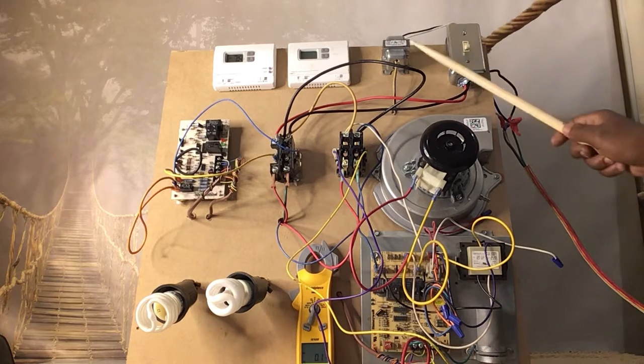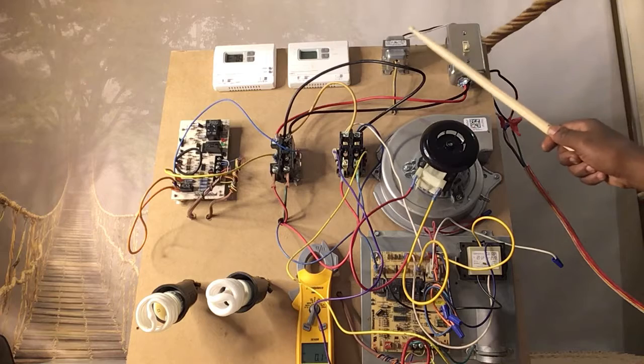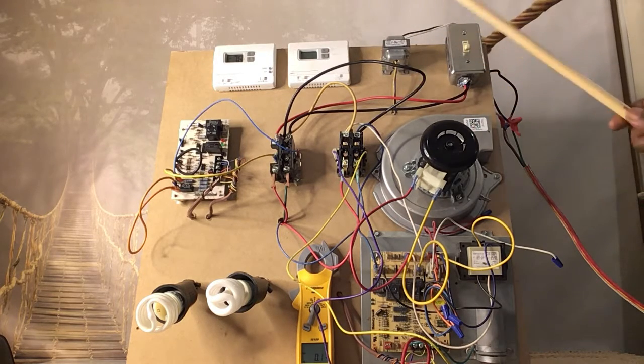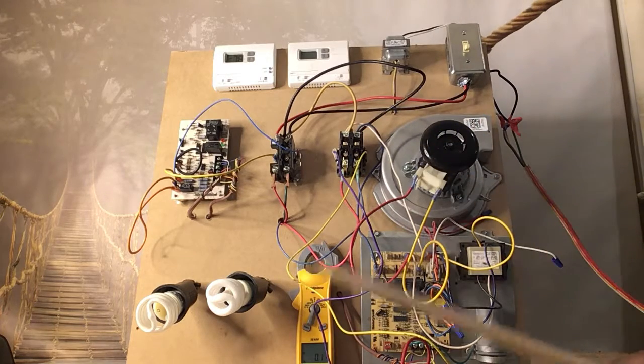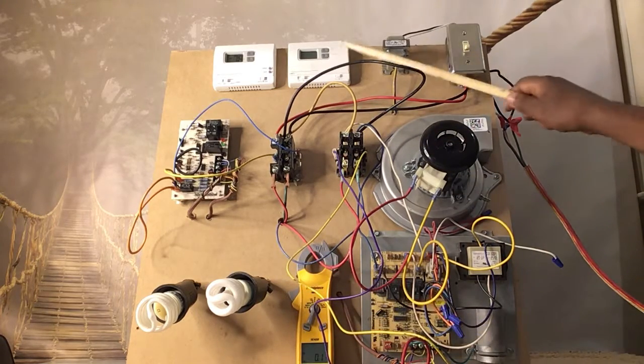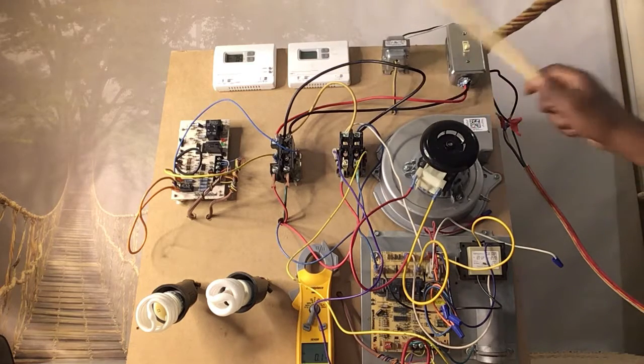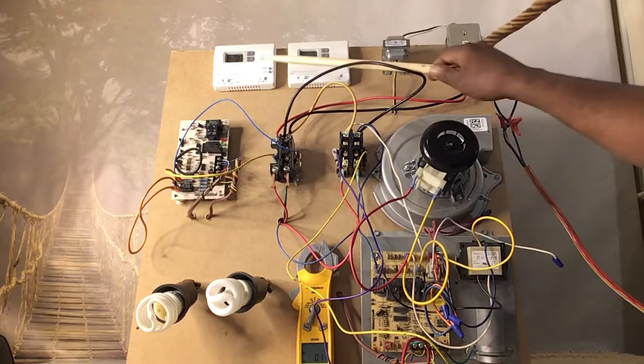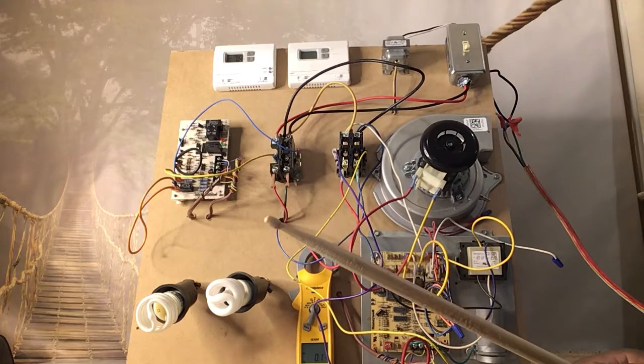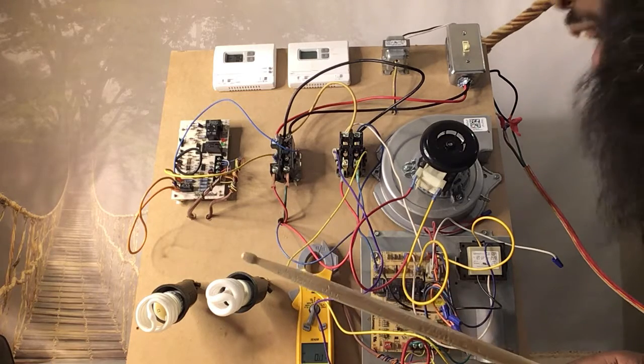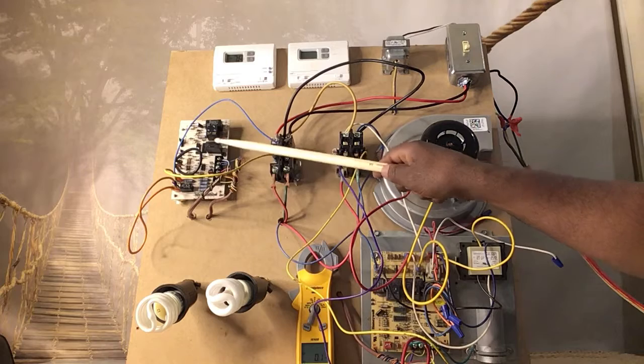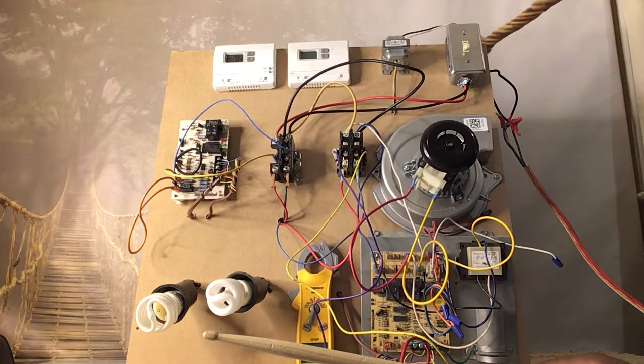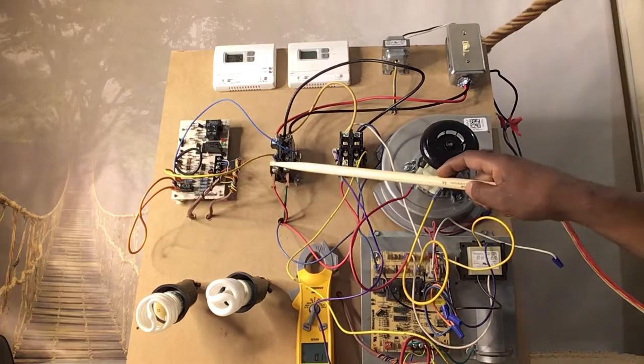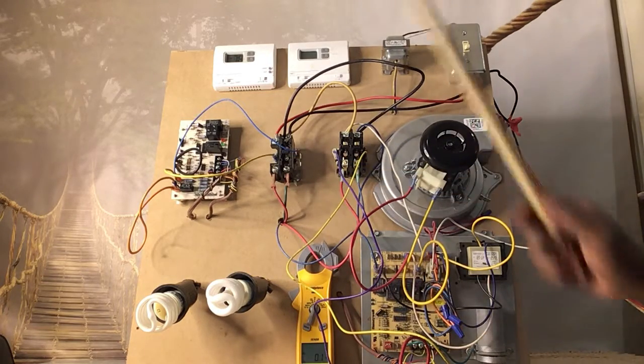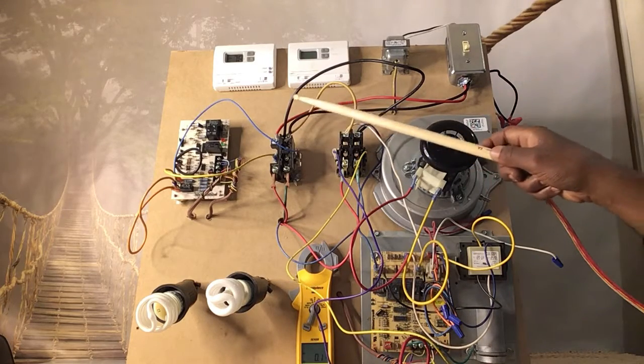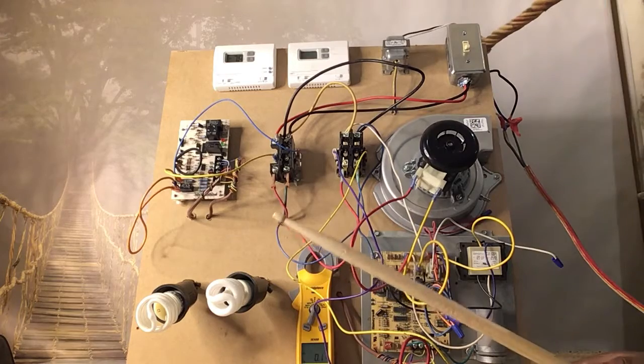This will be a step down transformer. It goes from 120 volts down to 24 volts, which actually controls a lot of your basic controls in your heating and air conditioning system. This right here would be a thermostat, which will only be for one heat, one cool application. This other thermostat will be for a heat pump application, and that is your outdoor unit doing air conditioning and heating. This right here will be a defrost control board that you would find inside of a heat pump system, along with a contactor. What it does is just pass voltage from one side to the next after 24 volts is applied to it. But we are going to get into all of that.